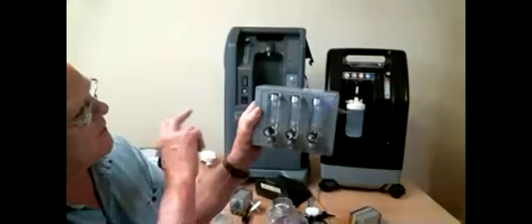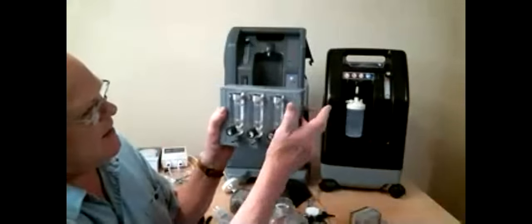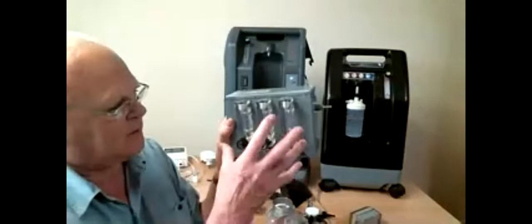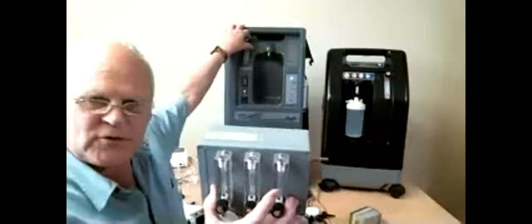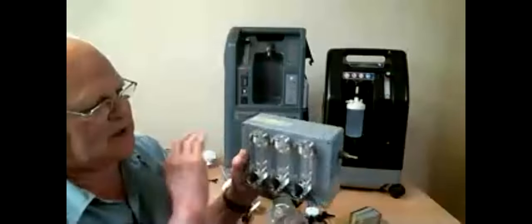You get more sophisticated flow splitters. So with this one, we've got an inlet in here and three flow meters on here for 5 liters each. But just to confirm, putting 10 liters in to a three-way flow splitter doesn't mean you're going to get 15 liters out. You will still only get the maximum on here, and you have to be careful not to dial up too much beyond the scope of the concentrator.